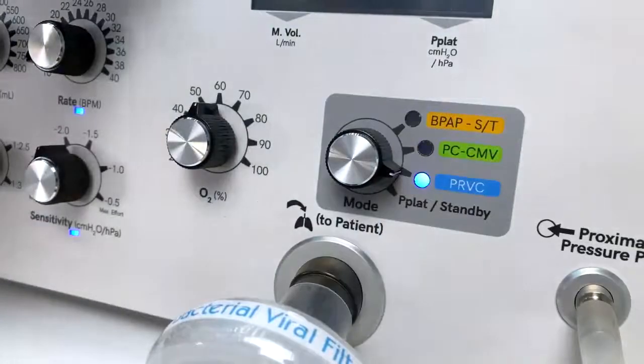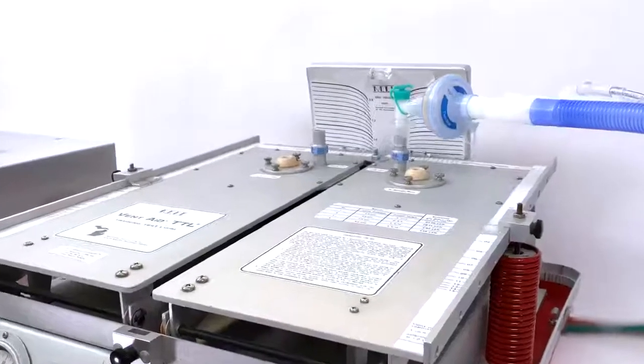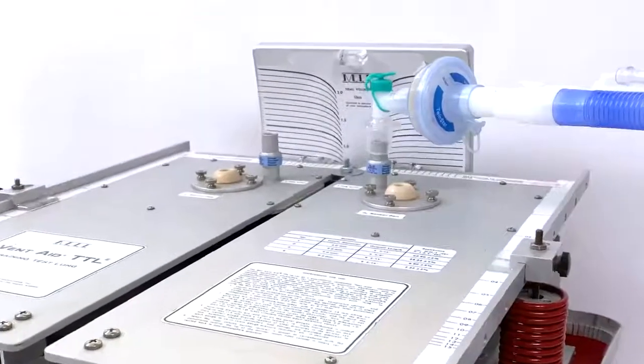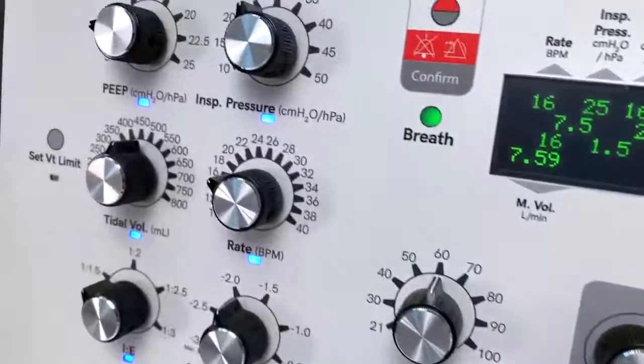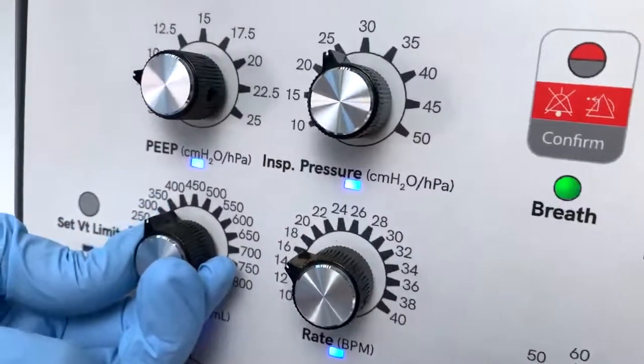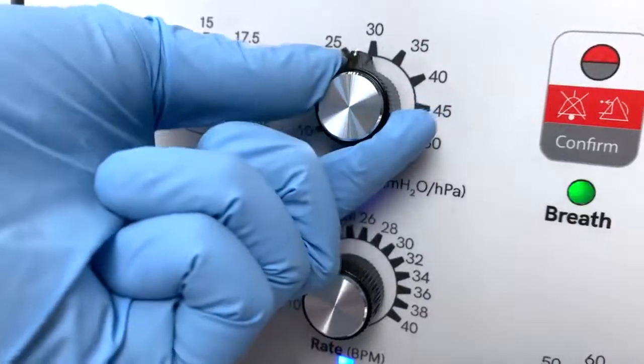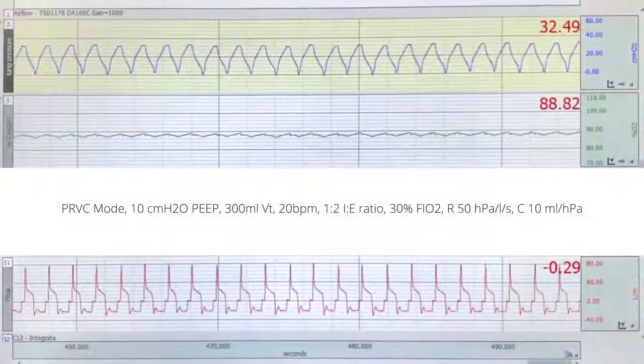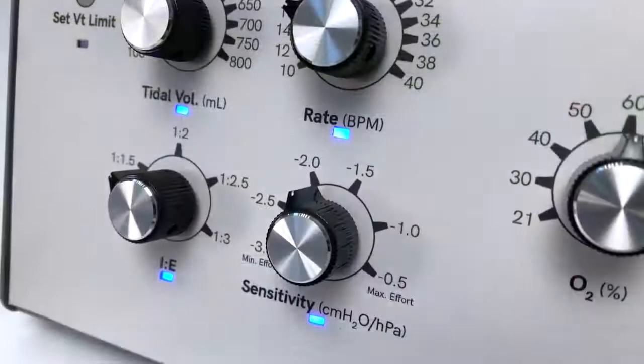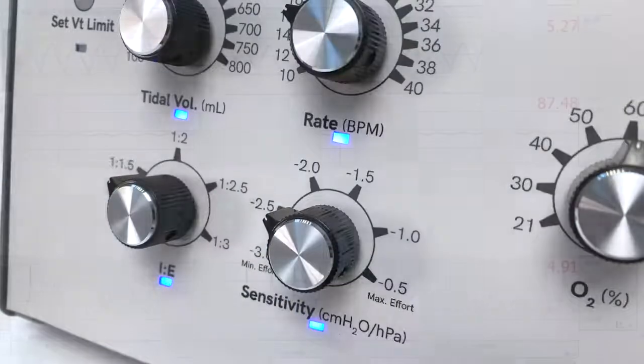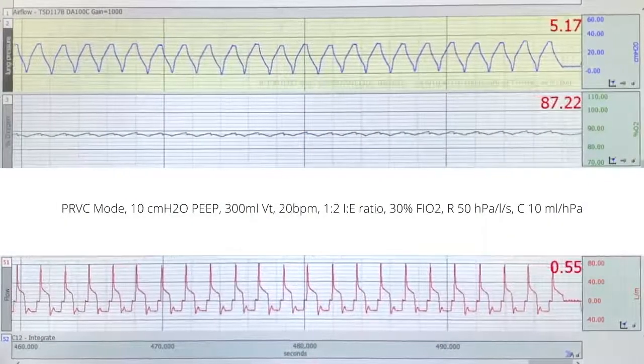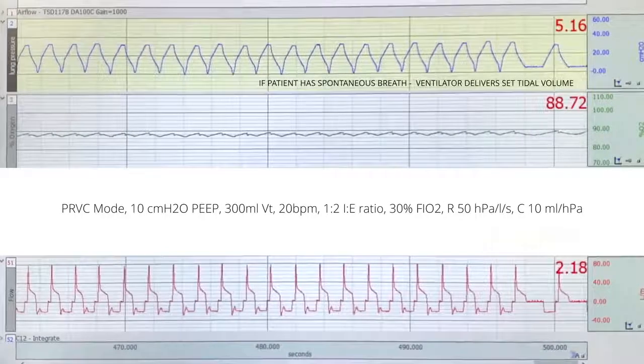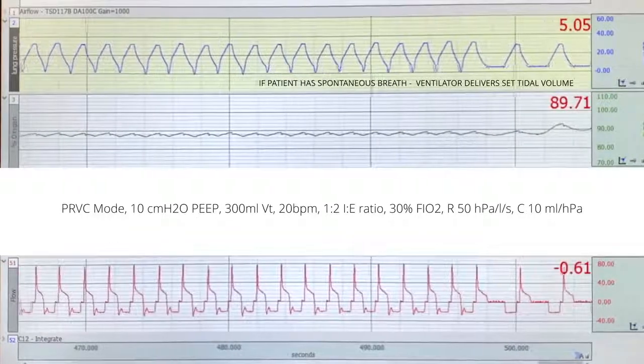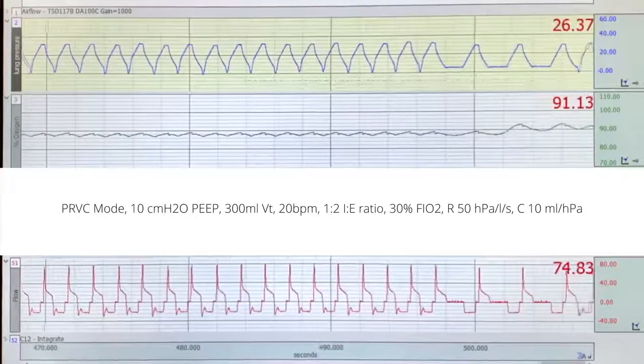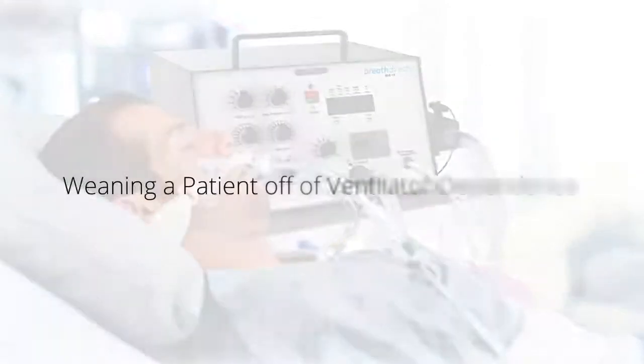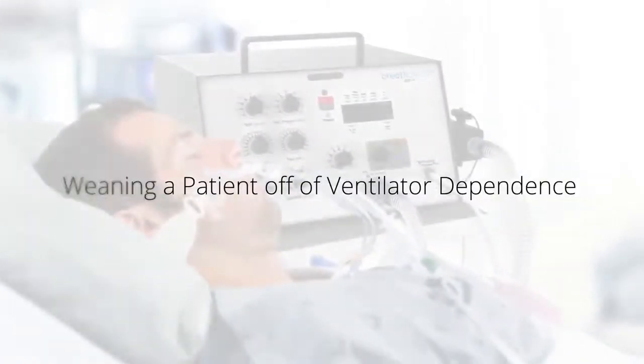PRVC mode is a volume-controlled, pressure-regulated mode that delivers mandatory breaths at the set tidal volume, PEEP, rate, IE ratio, and FiO2. For mandatory breaths, the user sets a desired tidal volume to be delivered by the ventilator. The user also sets a maximum allowed inspiratory pressure for additional safety. The patient can also trigger an assisted breath in this mode. For these assisted breaths, the user sets the assist sensitivity setting. If the patient has a spontaneous breath effort that reaches the set value, the ventilator will deliver the set tidal volume. The timing of mandatory breaths will be synchronized with the assisted breaths and the patient's own spontaneous breathing efforts. PRVC mode is very useful to begin to wean a patient off of being dependent on the ventilator.